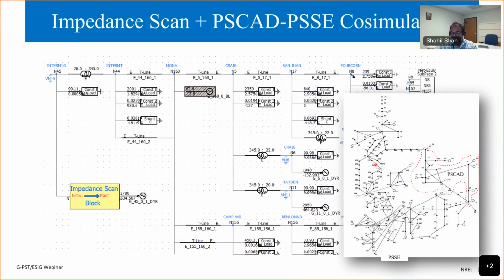We are using this in one DOE sponsored project. We are using this combination of PSCAD, PSSE co-simulation and impedance scan tool to understand how offshore wind generation that is planned in the Atlantic region will impact the stability of the onshore grid, because we have really good models of the onshore grid in the phasor domain, but vendors will be able to provide good models, or models which are accurate even at high frequencies, in the EMT domain. So we can combine the strengths of co-simulation with the impedance scan.